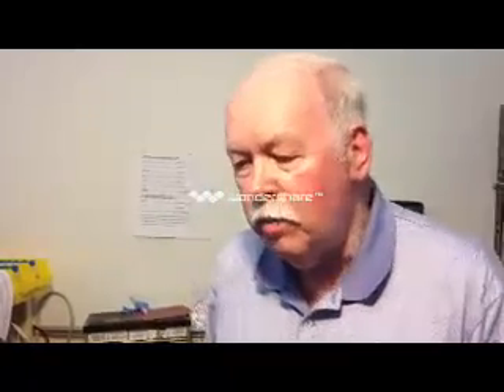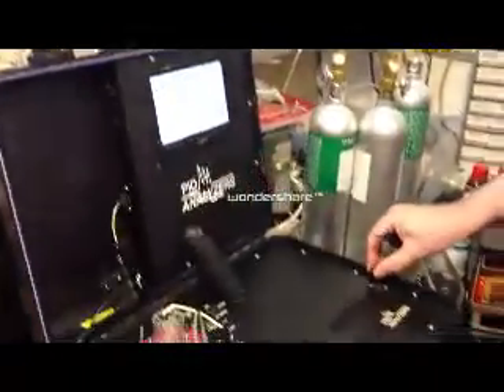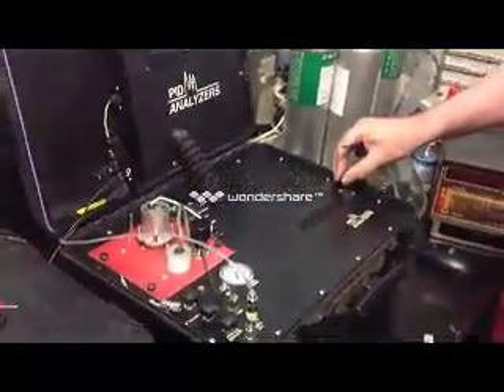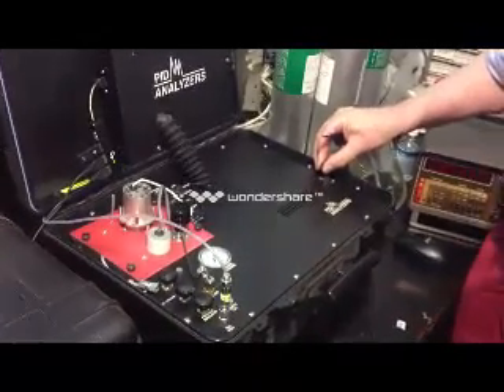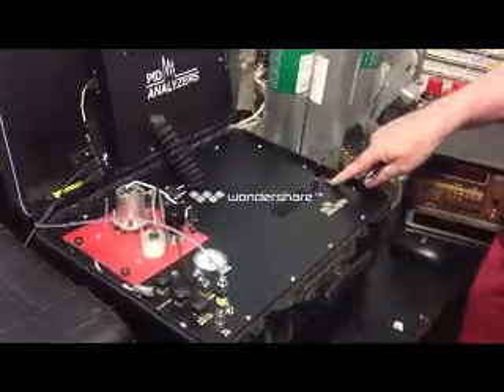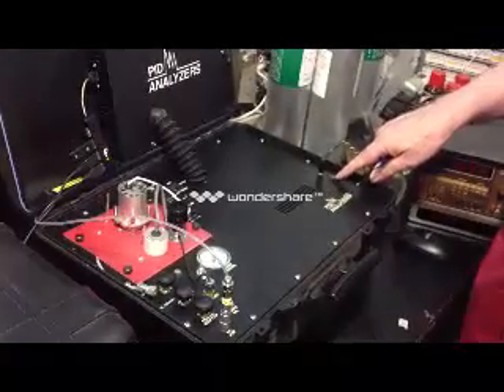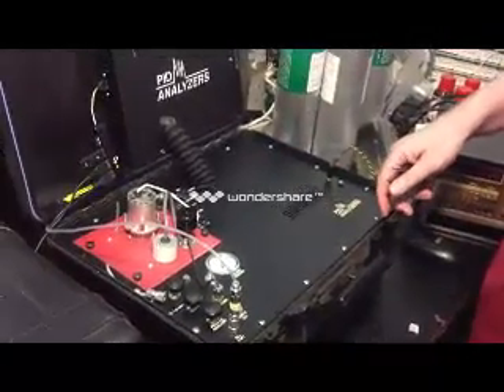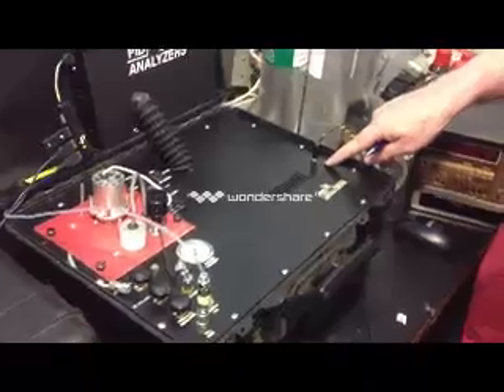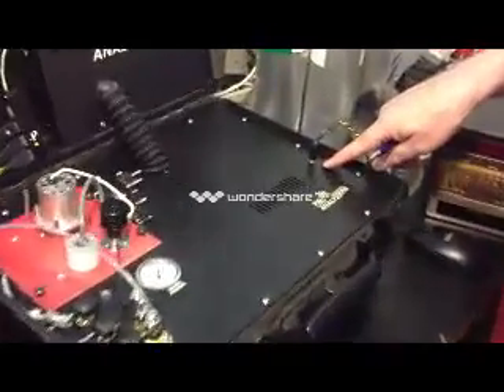This is the PID Analyzers model 312 gas chromatograph. This instrument can either be line operated, powered from 90 to 240 volts, or it could also be powered by battery. It'll run 6 to 8 hours on a battery, and there's a charger for the battery.